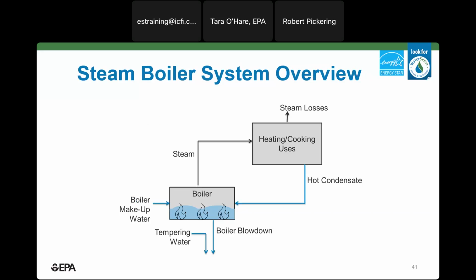Where this does vary from cooling towers is that this blowdown is really hot. And frequently it requires a tempering water stream that is mixed with the blowdown to reduce the temperature below 140 degrees Fahrenheit, so it can be discharged to the sewer. And this is based on local codes. So makeup water is then provided to make up for steam losses and the boiler blowdown.